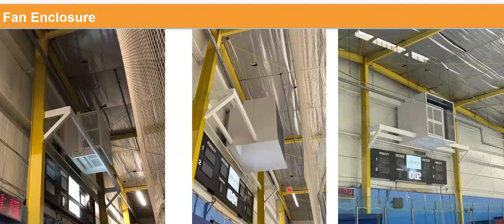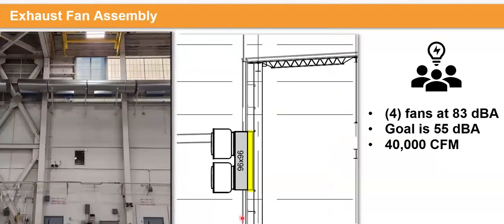We took all the drawings as is built, and we were able to provide the panels pre-cut right from factory to make sure that it was ready to install by the installing contractor right when he arrived on site. This has been installed, it's been working well. One thing that did happen was we had to look at manufacturer clearances to make sure that we were not breaching any warranties on the fan in terms of what spacing we needed to be around that exhaust fan in this scenario.